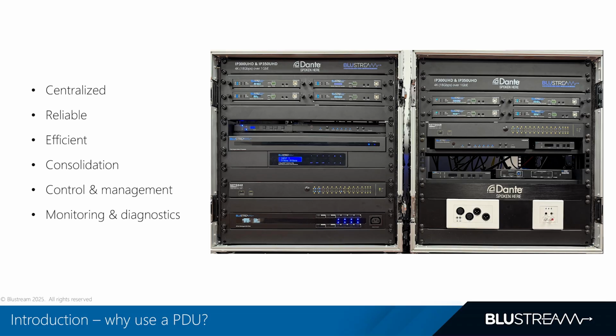Blustream PDUs add surge suppression and filtering to help shield sensitive gear from spikes and noise that can cause instability or long-term damage. Second, control. Because they're IP managed, you can see real-time status, cycle a locked-up device, or sync with a full rack remotely—no truck roll required. Sequenced power up and power down also prevent inrush current that can trip breakers or stress amplifiers.